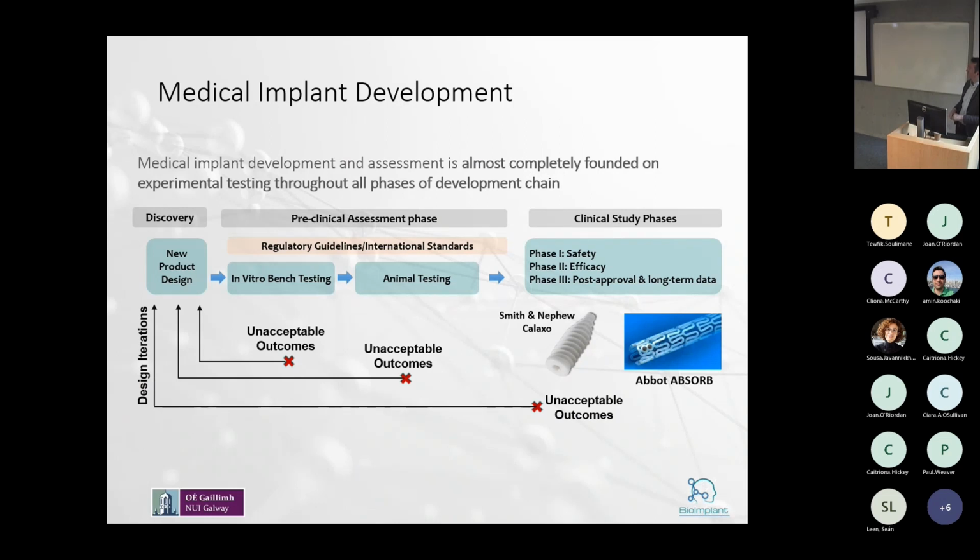And in terms of bioresorbable materials, there have been several famous cases where bioresorbable implants failed in post-market surveillance. There's an ACL screw from Smith and Nephew that failed after it was clinically approved, and also the Abbott Absorb device, a vascular device, which failed from poor late-stage clinical data that emerged 2 years post implantation.